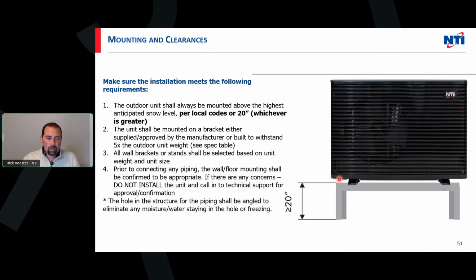What I'm more concerned with is at the bottom of the machine there's a bunch of holes, and those are drain holes. So when we go into a defrost cycle, if you're not familiar with defrost, I'll explain it real quick. As weather conditions get within a certain environment, if we have enough moisture in the air, we can start to form ice on the back of this coil, right? We have to melt that ice at some point. We have to make sure that when that ice melts during that defrost, it has a way to exit the machine, get out of there.